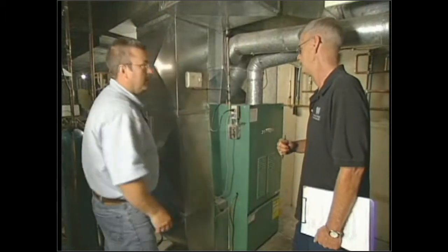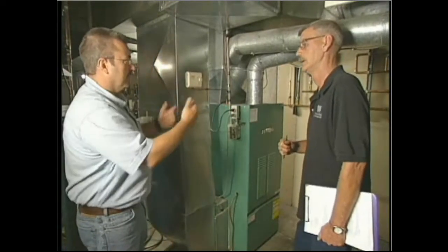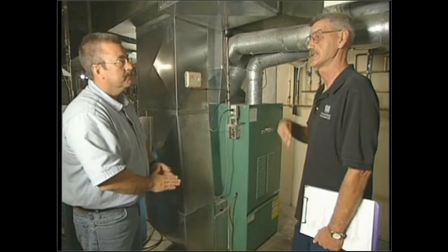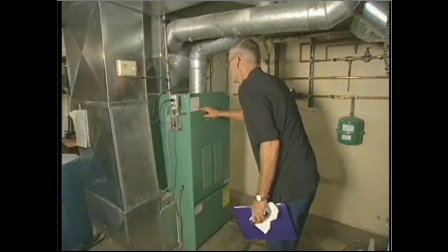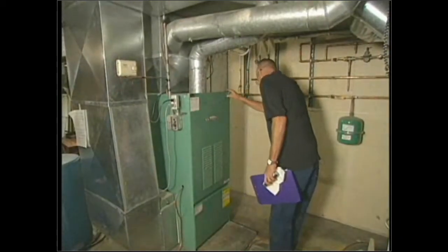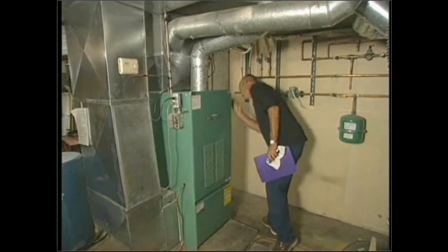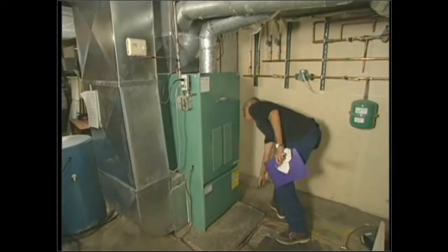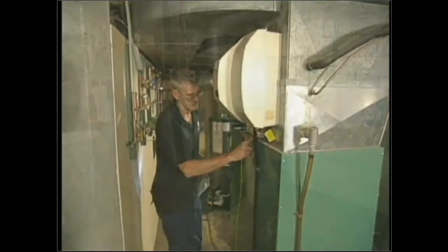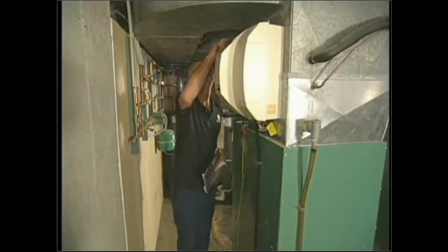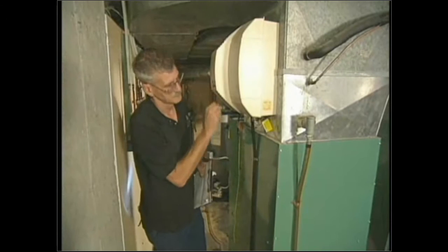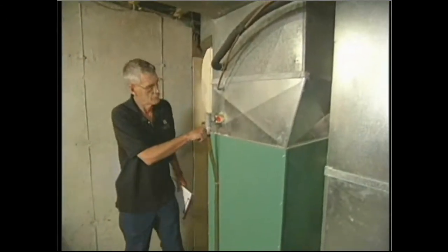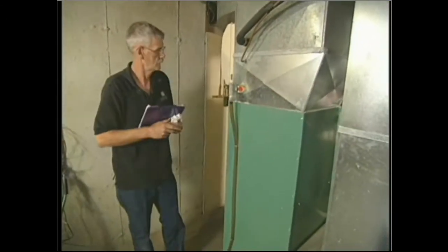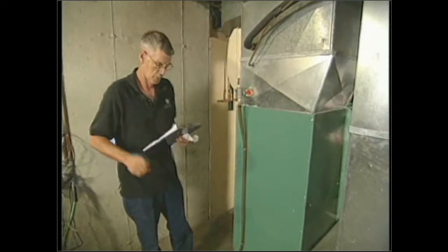We get to the unit itself. What about an exterior visual inspection? Well, I do the same visual inspection of the exterior, just like we do for the 70s, the 80s, and the 90s and the gases. I'll walk around, I'll document for rust, I'll look for signs of discoloration in the paint. When I have discoloration in the paint like we did for the 80s and the 90s, that's possibly a sign of a cracked heat exchanger. And it's more prominent in an oil because of the higher temperatures inside the flue gases.